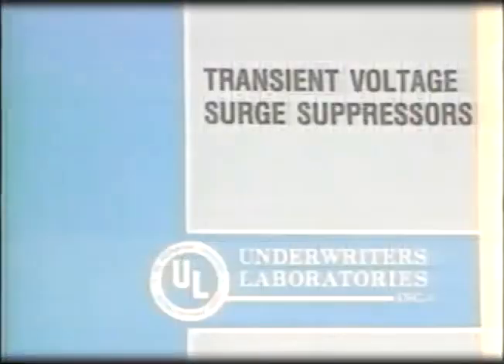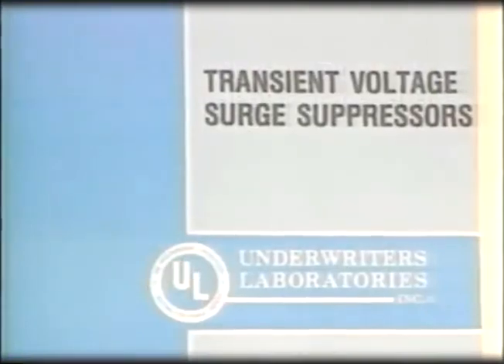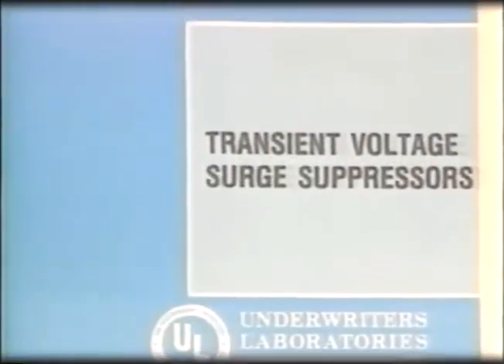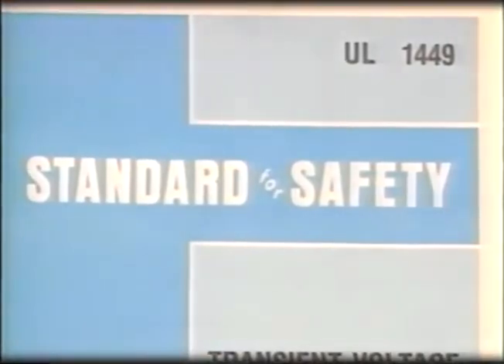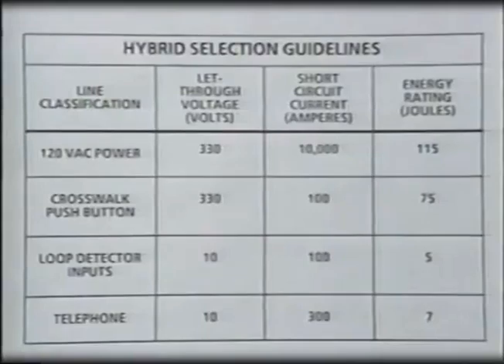If you specify suppressors that meet UL 1449, be aware that the lightning test conditions specified in UL 1449 are not as severe as the specs in NCHRP 317. And be sure to get certified test data and circuit schematics, so you know what you're buying. Also help other maintenance and repair personnel. The guidelines in the user's manual can help you select the combination that's best for your particular situation.